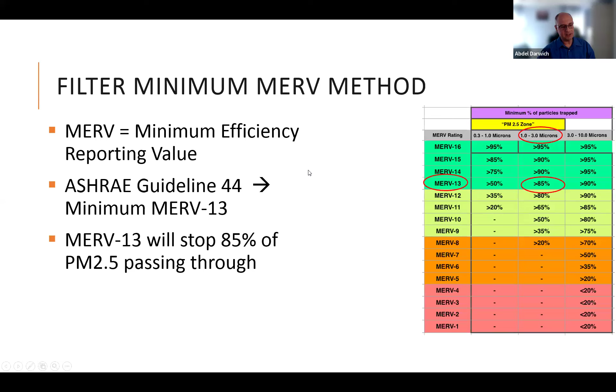Some other filter consideration is that you need to change the filter very frequently during wildfire smoke, because it will get dirty very, very quickly. In ASHRAE Guideline 44, we give a method of how you can estimate this. I will not go over it now for lack of time, but irrespective, you have to anticipate changing the filter very frequently. I've seen some hospitals changing filters as frequently as every 2-3 days, but they were in very bad wildfire smoke situations. A lot of them change it every 1 or 2 weeks, versus normally you would change them every 3 to 6 months.